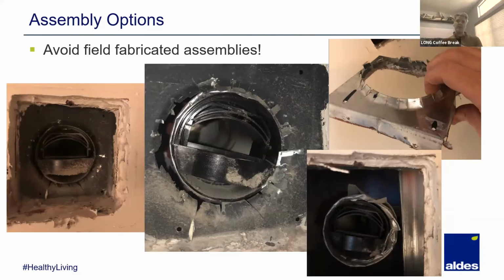Absolutely. Now, when you install this, Scott, what does a balancer need to do in order to assure that it's working properly? Yeah, so when we see these projects, obviously, we definitely promote some savings on the balancing side, right? If you're ordering it factory set, then what's the point of ordering it factory set if you just have to go back and balance it? So, we certainly recommend doing spot checks. It sounds oversimplified, but I always tell people to check at the extremes. Check at the bottom, check at the top, traverse the riser, get at minimum those 3 measurements, because if it's working at the bottom and it's working at the top and you traverse the riser and, if you're supposed to be getting 1,000 CFM and you're close to 1,000 CFM, there's no way that it's not working, right? That's the easiest way to look at it.